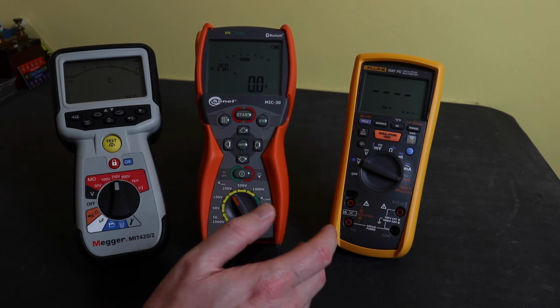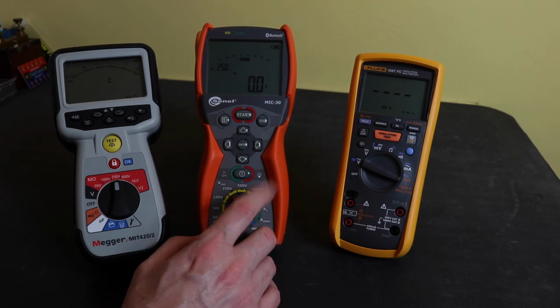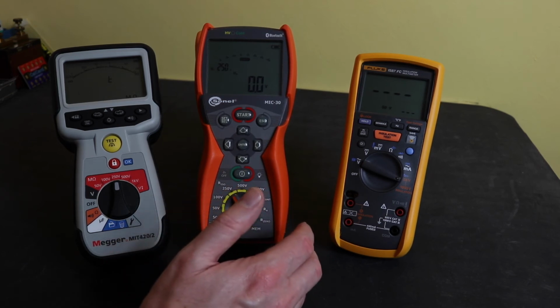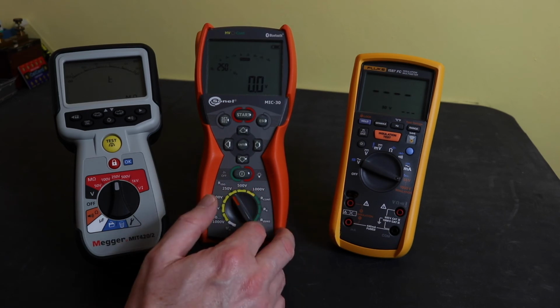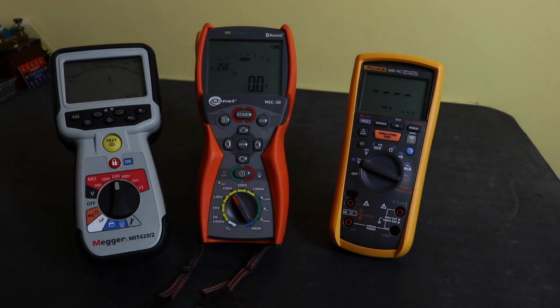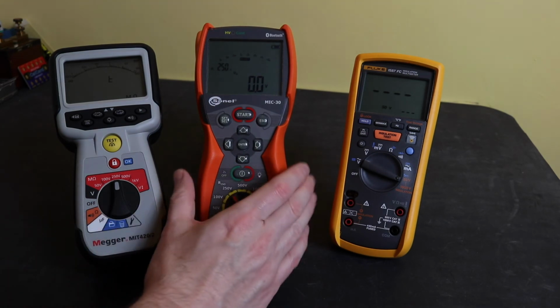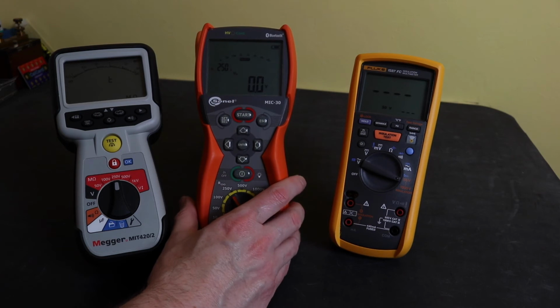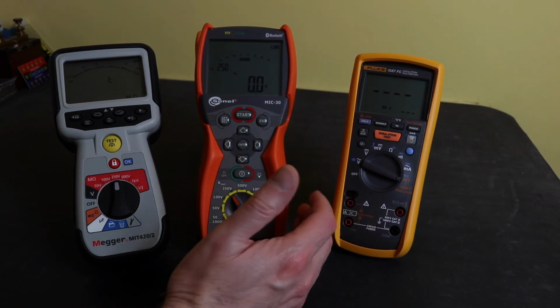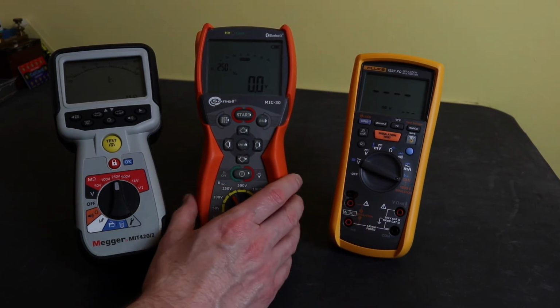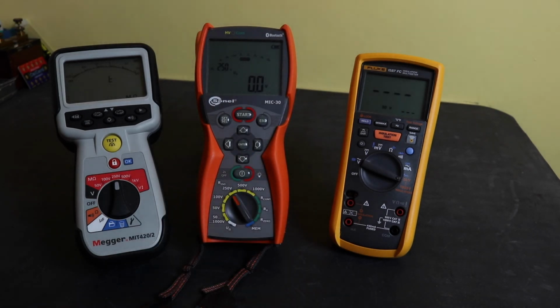Occasionally, the worst case I've been, so I say the worst, the best case I've been up to is around 8 for a polarization index. I think I was on around about 30 gigaohms, 35 gigaohms at the 10-minute mark. So that would be out of the reach of this instrument, but it would probably cover sort of like 75% of the testing that I do and scenarios that I've come across.